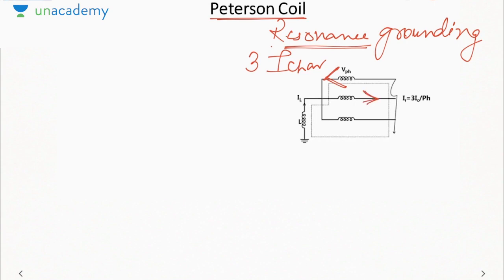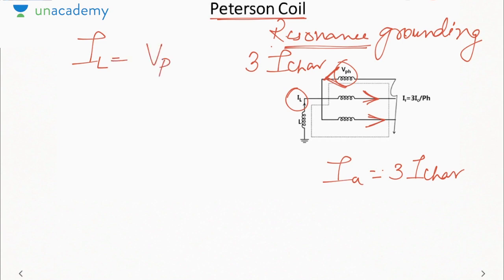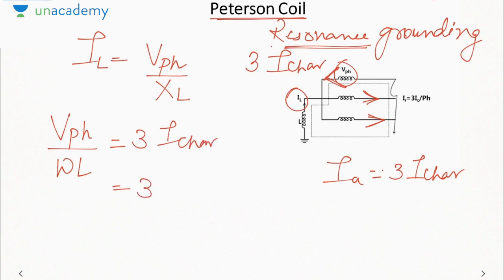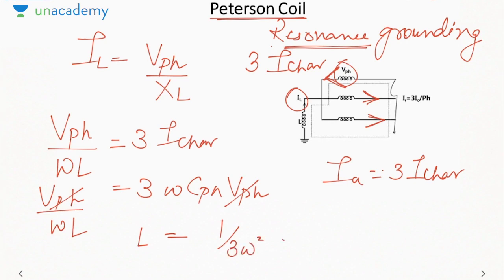That was being divided into the two phases. Here I have grounded the A phase, so IA will be equal to 3 times I charging. When we were doing the derivation, then we were grounding the C phase, so C phase current was coming out to be 3 times I charging. Now this current should be cancelled out by this IL. So IL is actually V phase by XL. It should be equal to 3 times I charging, which is equal to 3 omega C phase V phase. 3 times I charging we derived earlier only. It should be equal to V phase by omega L. So here L will be equal to 1 by 3 omega square C.